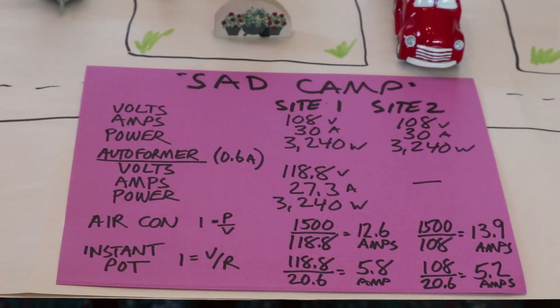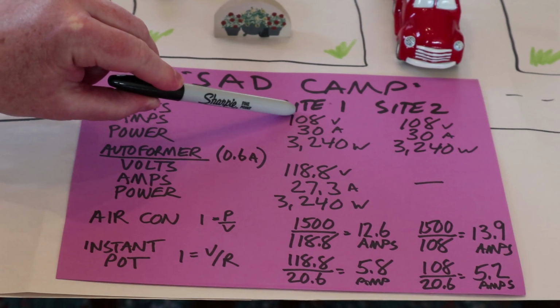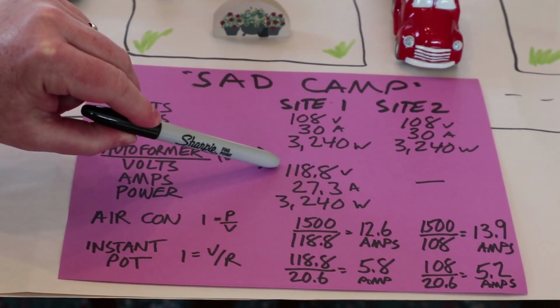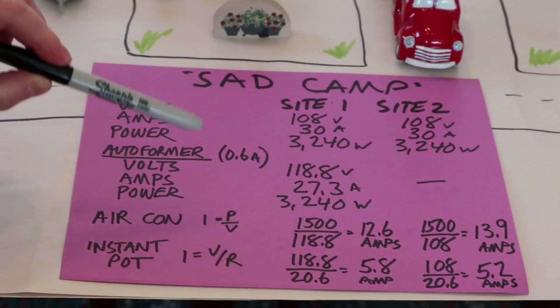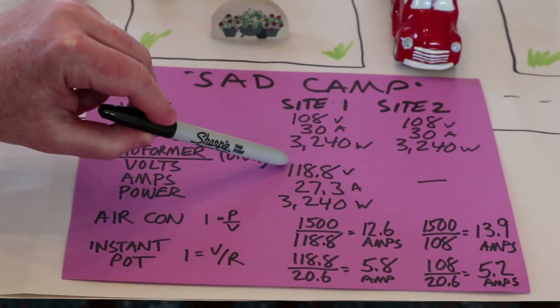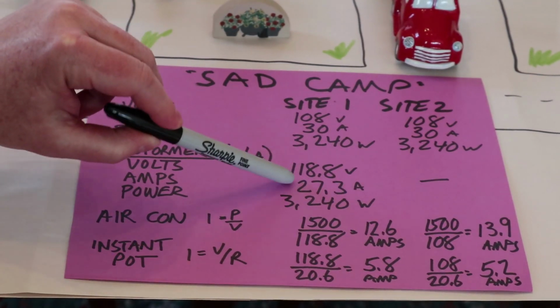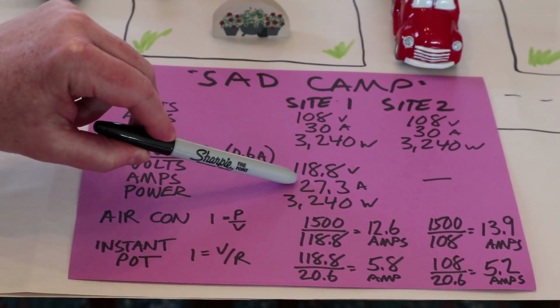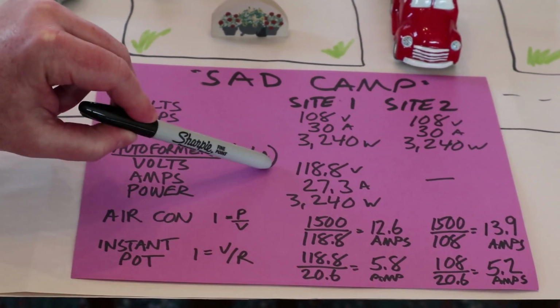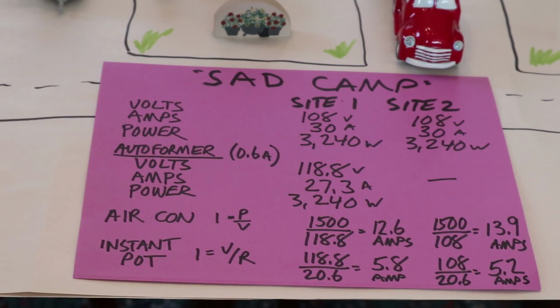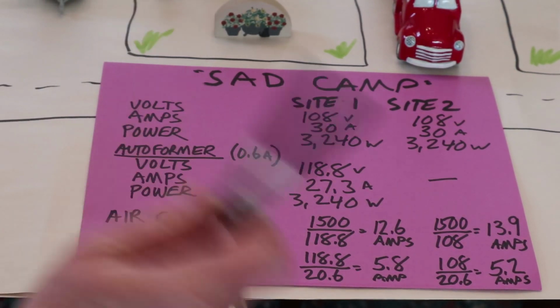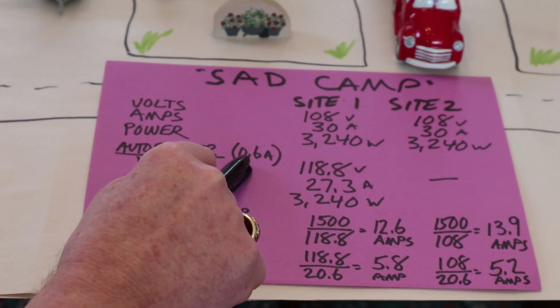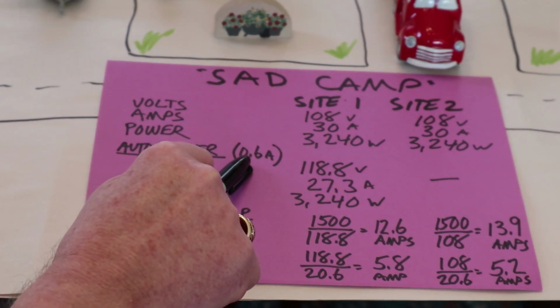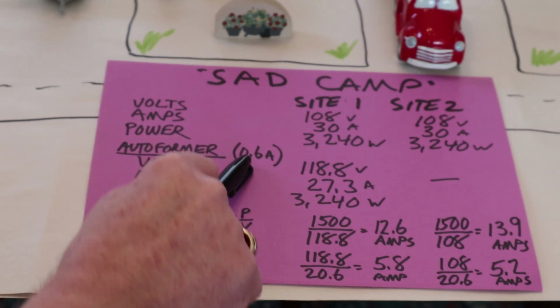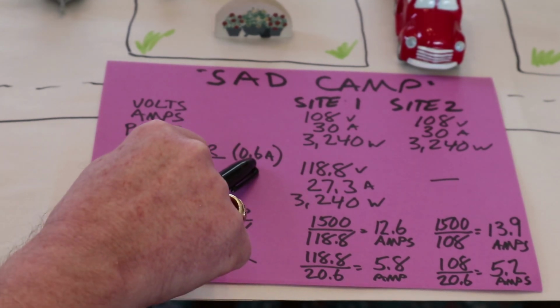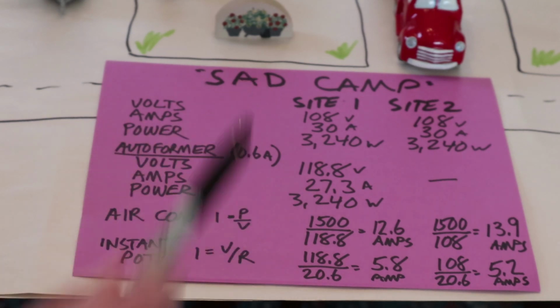The autoformer is going to recognize that the voltage is low and boost that voltage to 118.8. However, as we found, that 10% increase in voltage results in a 10% decrease in amperage. The power available is still the same, but now I only have 27 amps that I can pull. I will note, however, that the autoformer does have some energy loss in the form of heat and impedance, so it draws about 0.6 amps, and we'll include that in the calculations.